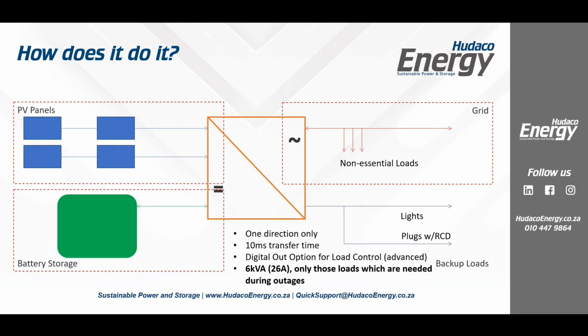Okay. And when we talk about the 6 kVA unit, we are only referring to this backup port. It's 26 amps on the single phase unit. Okay. So a lot of guys will come in and say, oh, it's a 6 kVA unit. It's not a 6 kVA unit. The 6 kVA refers just to the amount of load that we are going to run on batteries during failures. The majority of our clients actually don't exceed 2, maybe 3 kilowatts on their loads during outages.